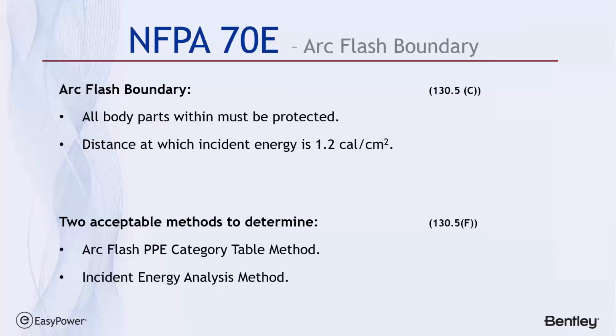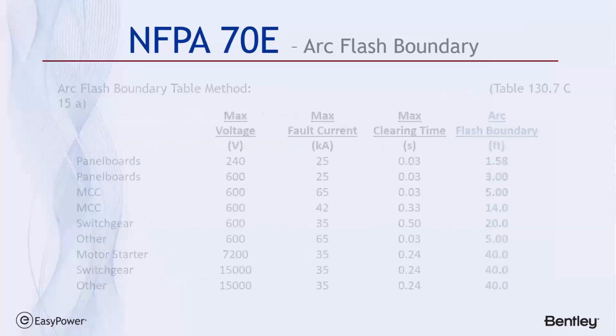So we've defined the arc flash boundary. There are two acceptable methods to determine the arc flash boundary. One is the arc flash PPE and arc flash boundary lookup table, and the second is incident energy analysis. We're going to be focusing primarily on the second, but I'm going to touch base on this table lookup.